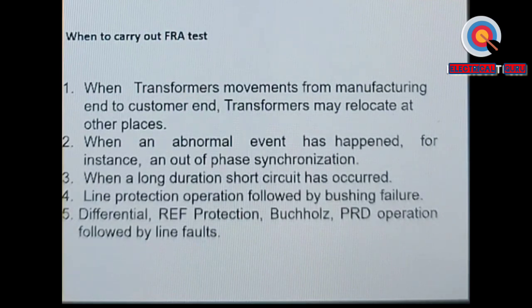The test is also done when an abnormal event has happened, for instance an out-of-phase synchronization. Of course, nowadays out-of-phase synchronization is very rare, but still sometimes errors do happen in connections. Most of the time this happens when the PT is connected in wrong polarity. When we are checking angle 0, if one of the PT polarities is reversed, then the 0 or 360 degrees we are seeing on the synchroscope is actually 180 degrees.